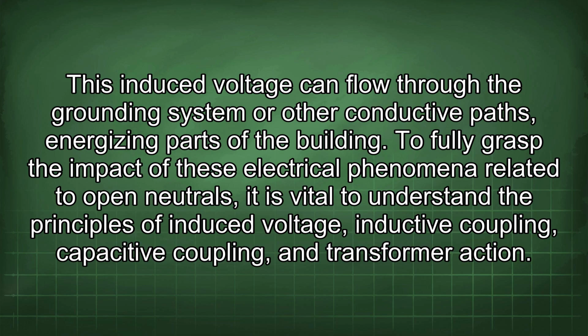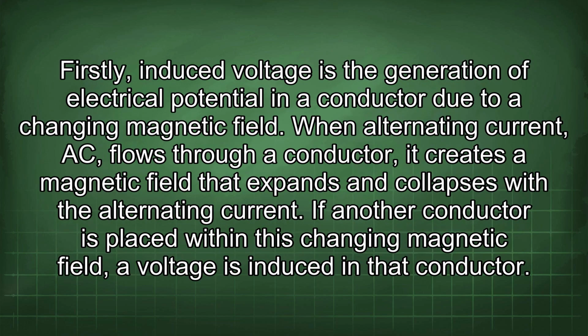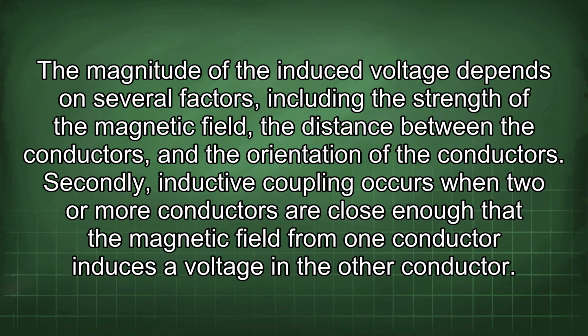To fully grasp the impact of these electrical phenomena related to open neutrals, it is vital to understand the principles of induced voltage, inductive coupling, capacitive coupling, and transformer action. Firstly, induced voltage is the generation of electrical potential in a conductor due to a changing magnetic field. When alternating current, AC, flows through a conductor, it creates a magnetic field that expands and collapses with the alternating current. If another conductor is placed within this changing magnetic field, a voltage is induced in that conductor. The magnitude of the induced voltage depends on several factors, including the strength of the magnetic field, the distance between the conductors, and the orientation of the conductors.